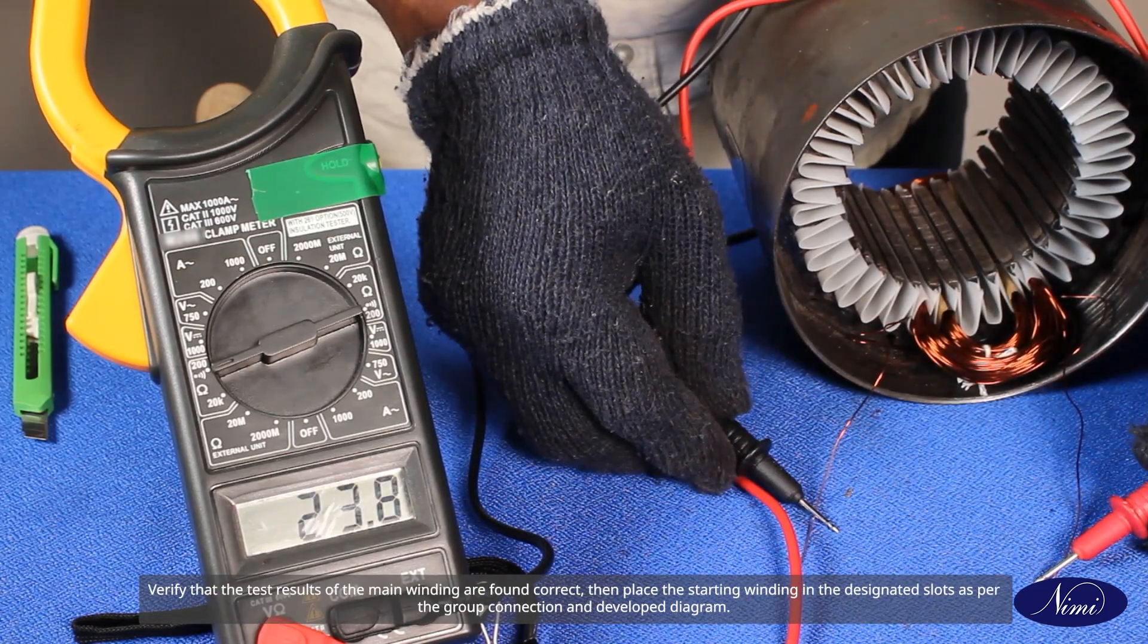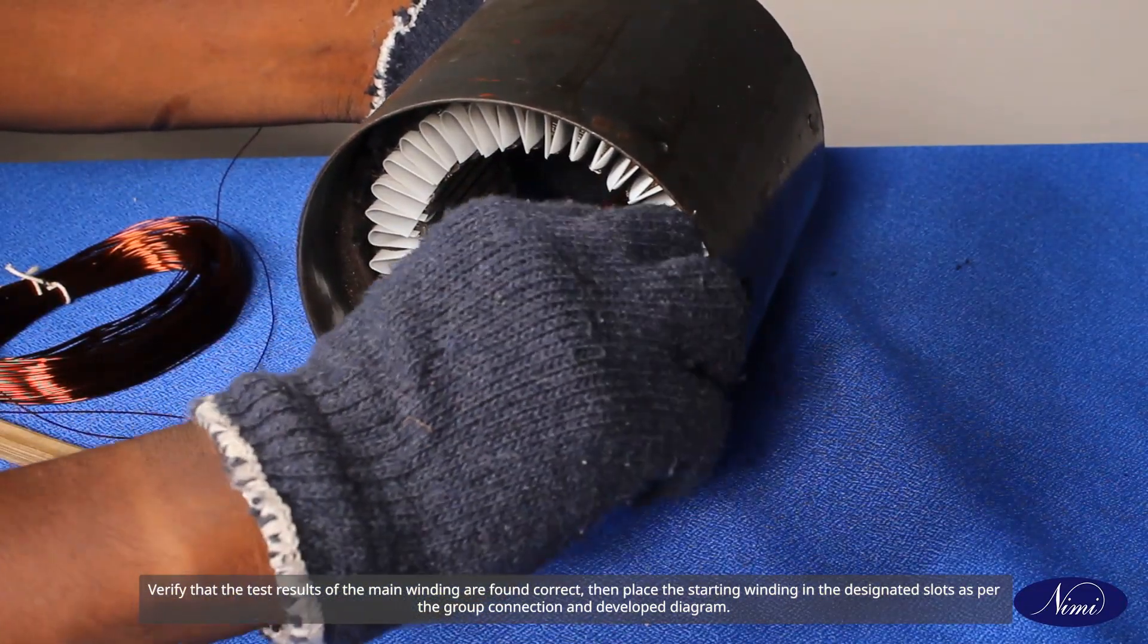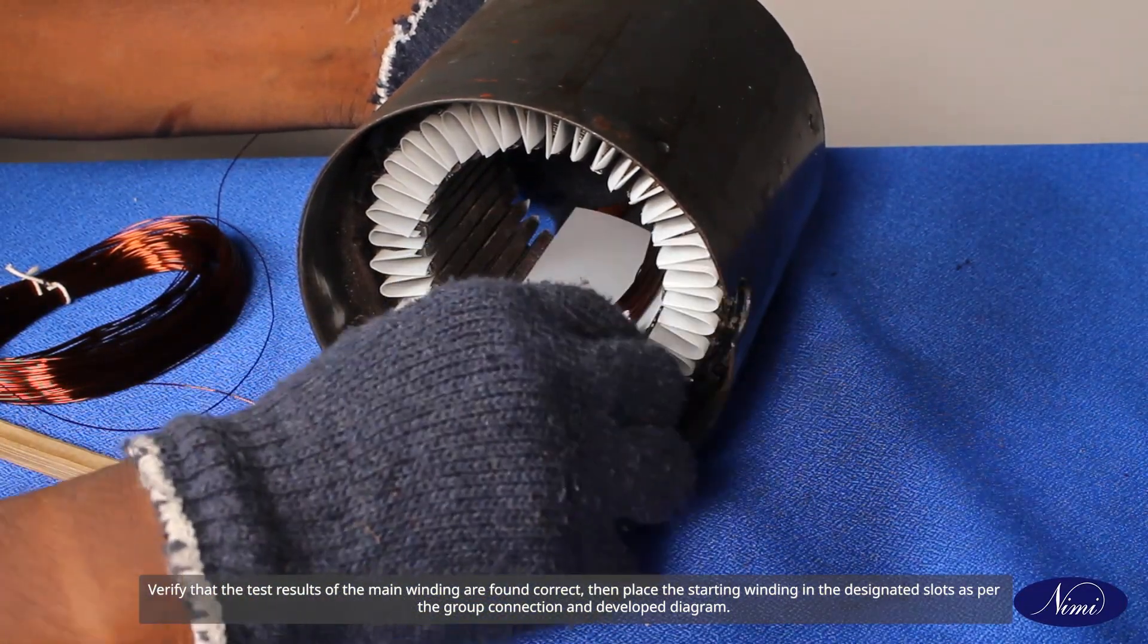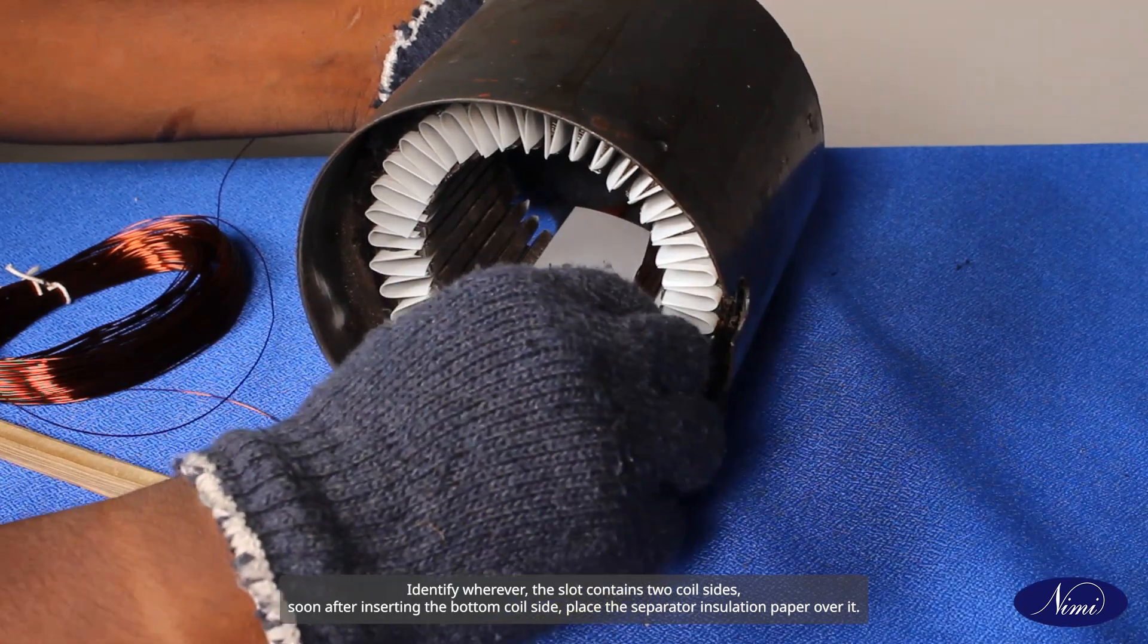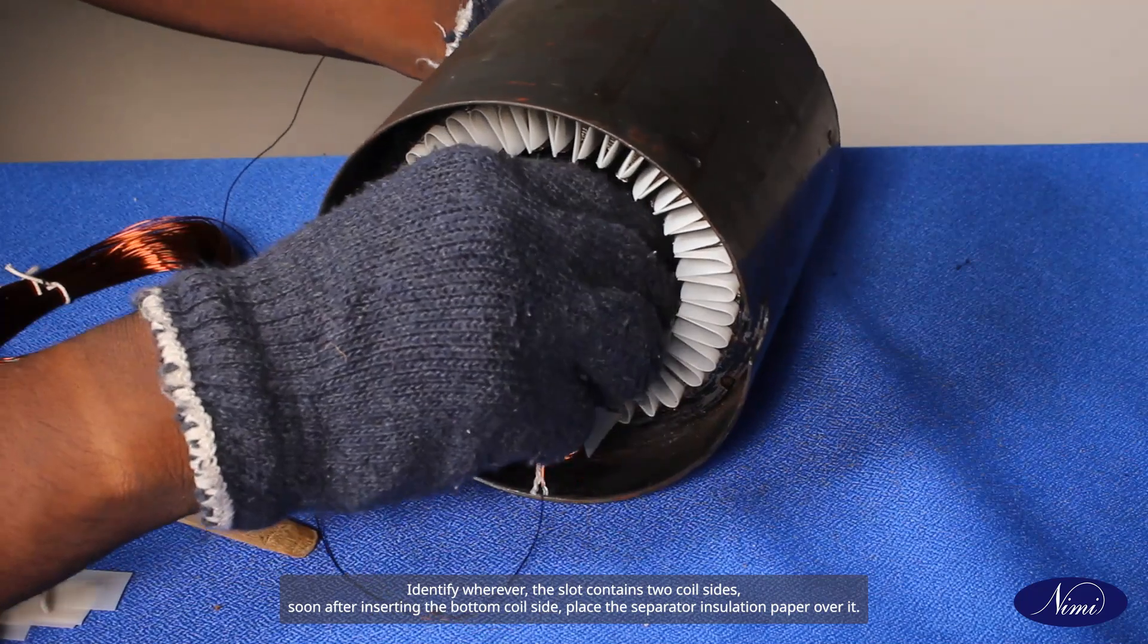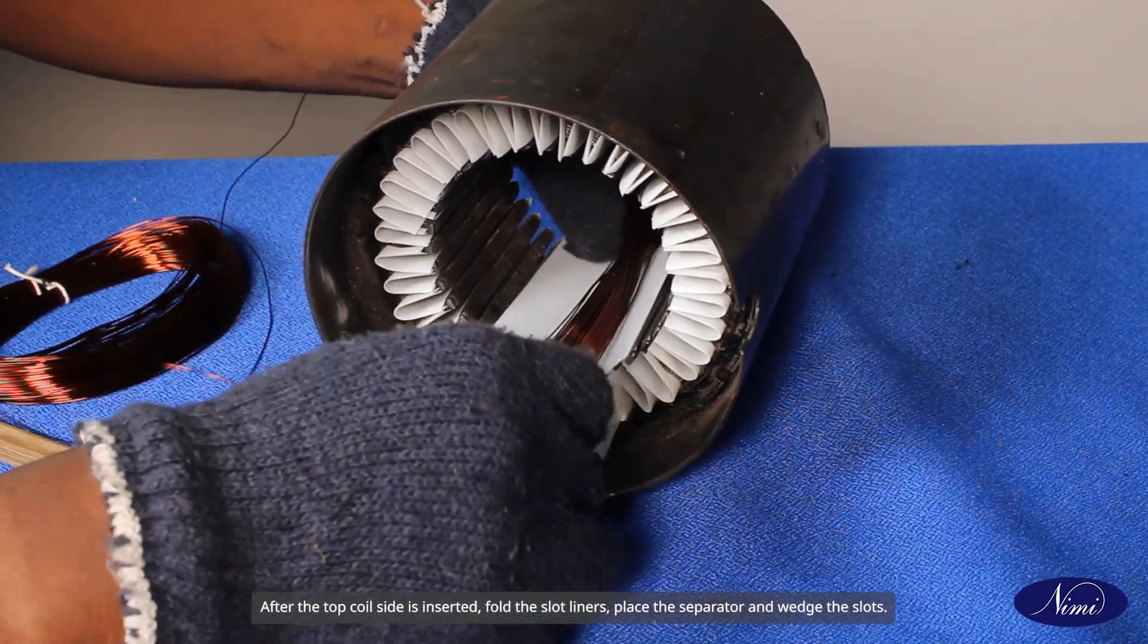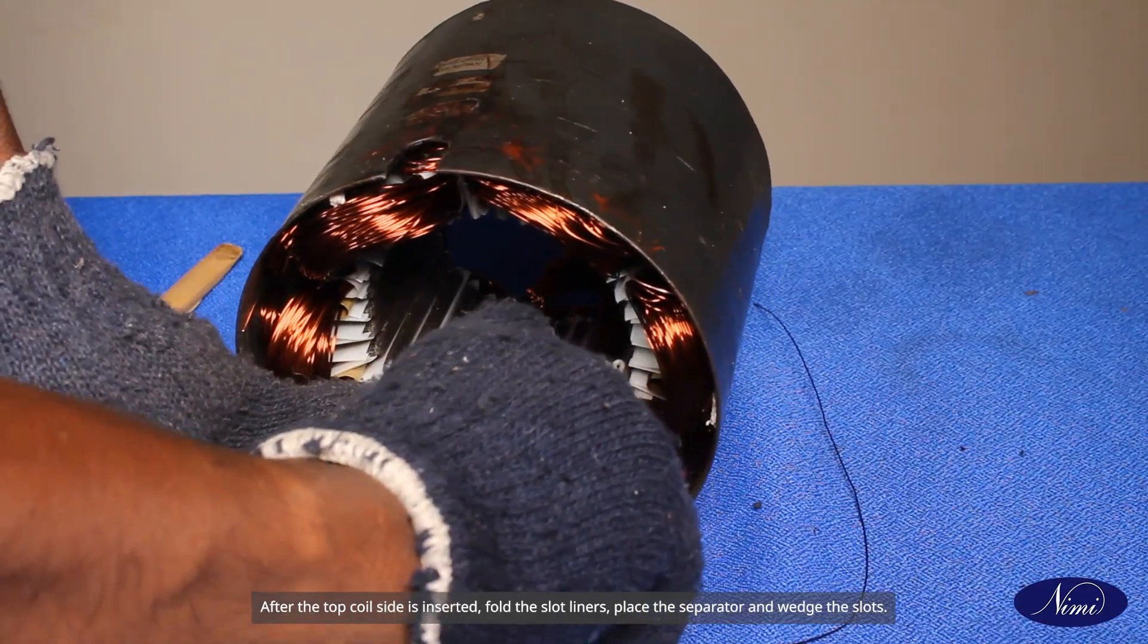Verify that the test results of the main winding are found correct, then place the starting winding in the designated slots as per the group connection and developed diagram. Identify wherever the slots contain two coil sides. Soon after inserting the bottom coil side, place the separator insulation paper over it. After the top coil side is inserted, fold the slot liners.